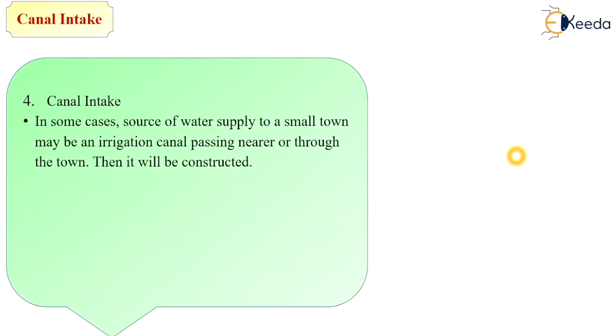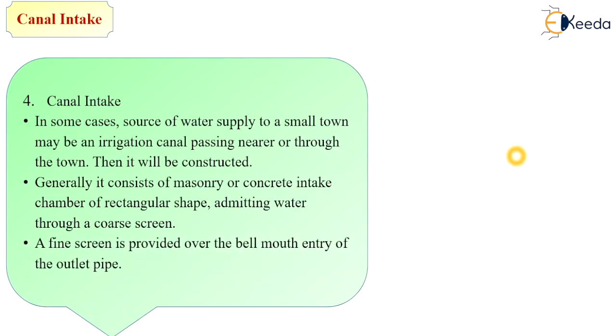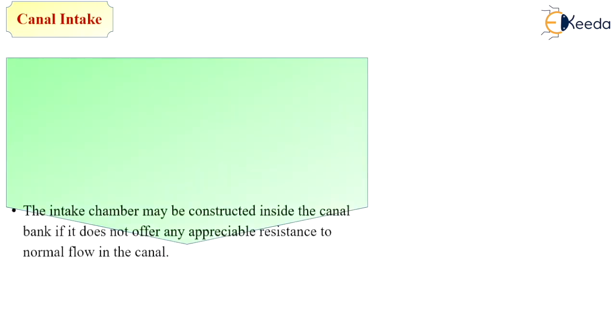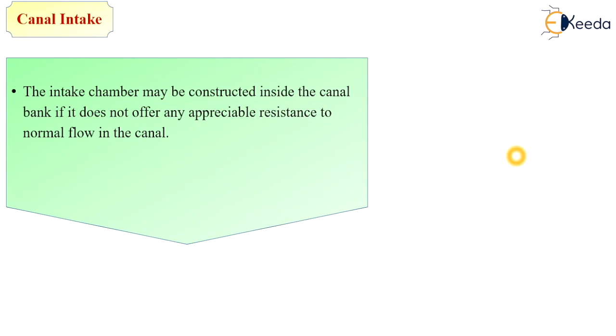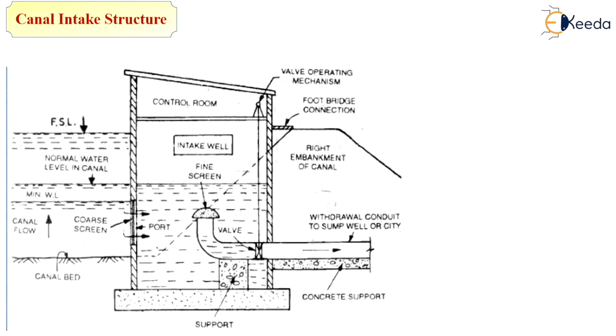Next is canal intake. In some cases, the source of water supply available to a small town may be an irrigation canal passing near or through the town. It generally consists of a masonry or concrete intake chamber of rectangular shape admitting water through a coarse screen. A fine screen is provided over the bell mouth entry of the outlet pipe to avoid silt content or floating material. The intake chamber may be constructed inside the canal bank if it does not offer appreciable resistance to normal flow. It is preferred to provide lining to the canal near the intake chamber to avoid leakage.